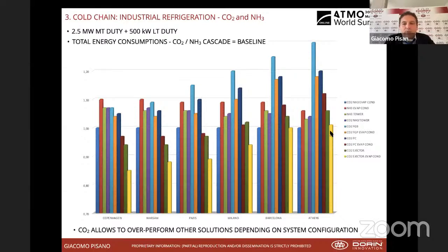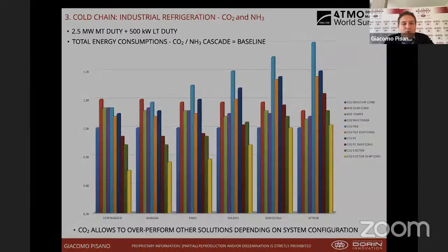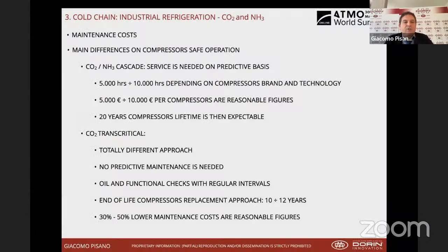Clearly adding on top parallel compression, evaporative condenser, ejectors, brings in a lot of cost. So the CO2 rack may not be so much convenient, as we said before, when compared to ammonia. So maintenance cost is also very important to mention. Let's say that when you talk about the typical CO2 and ammonia system using industrial compressors, service maintenance is needed on a predictive basis.